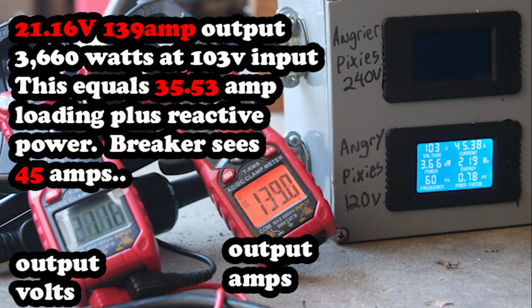I'm honestly shocked that the magnetic trip didn't trip, but a lot of times that's set at like 47 to 50 amps on a 20 amp breaker. So again, all of this pretty much adds up to the fact that these things suck, and you're not going to be running them on a generator anytime soon, and you're better off with a 240 volt welder. Hopefully all of that stuff makes sense for you.